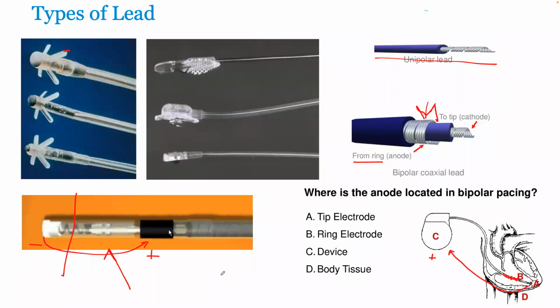So it's just a little tip there. If you do think you've perforated, program unipolar. And if you've got no capture, the chances are that your tip electrode is outside the myocardium. But you can be fooled sometimes in bipolar if you have perforated and still have capture, because it's such a small circuit with enough output, you can still capture around that ring electrode. So again, just something to look out for, and it can also be seen if you measure your injury current, you may get a negative injury current as the current is moving away from the electrode. Mm-hmm. So again, that's another indication that perhaps you have perforated.